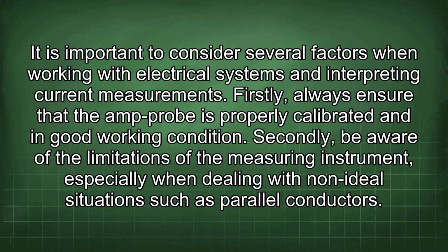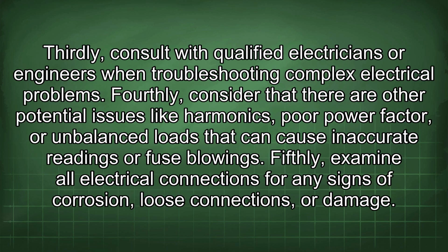It is important to consider several factors when working with electrical systems and interpreting current measurements. Firstly, always ensure that the amp probe is properly calibrated and in good working condition. Secondly, be aware of the limitations of the measuring instrument, especially when dealing with non-ideal situations such as parallel conductors. Thirdly, consult with qualified electricians or engineers when troubleshooting complex electrical problems. Fourthly, consider that there are other potential issues like harmonics, poor power factor, or unbalanced loads that can cause inaccurate readings or fuse blowings. Fifthly, examine all electrical connections for any signs of corrosion, loose connections, or damage.